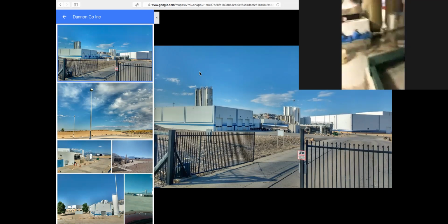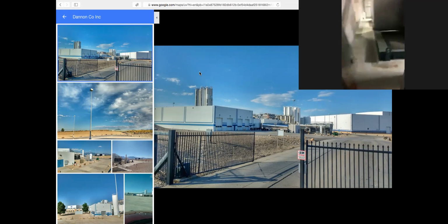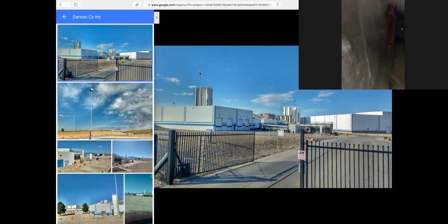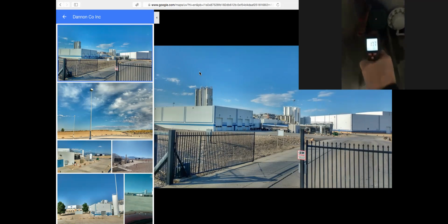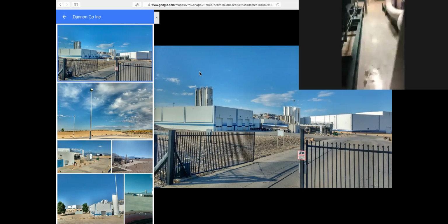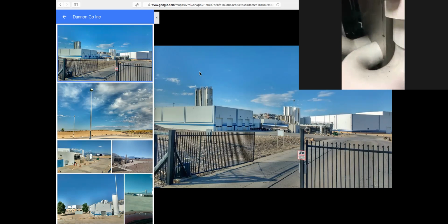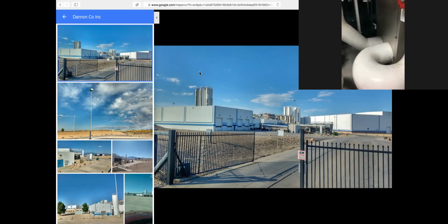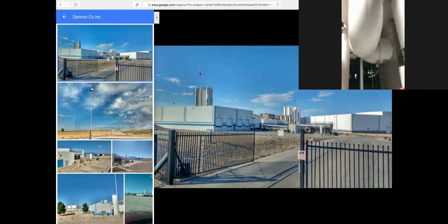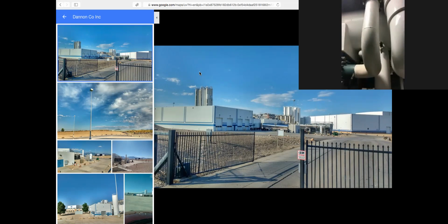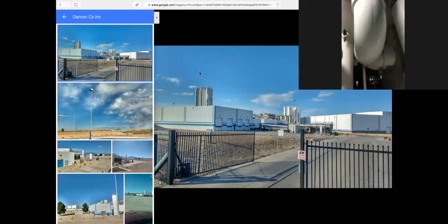And then over here on the cooler itself, there is a reading of about 17.4 degrees. That side has got the ice built up on it. It's about 14 degrees. Looks like it's coming down. The difficult part on the glycol exiting this is that they wrap it in so much insulation. Actually just the pipe. There's an insulated pipe, there's an uninsulated pipe. You can see they try to get around it for a while. It gets up to the chiller.